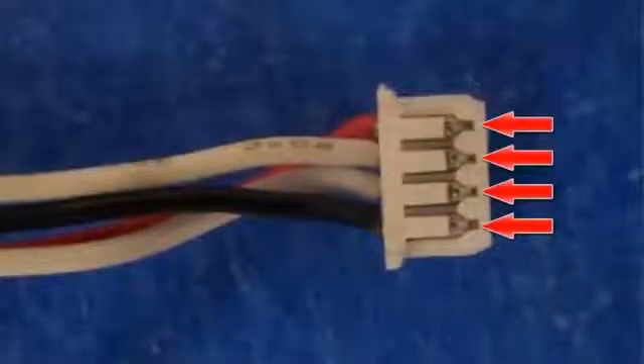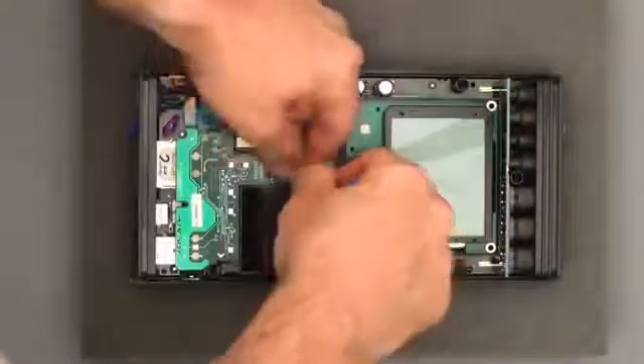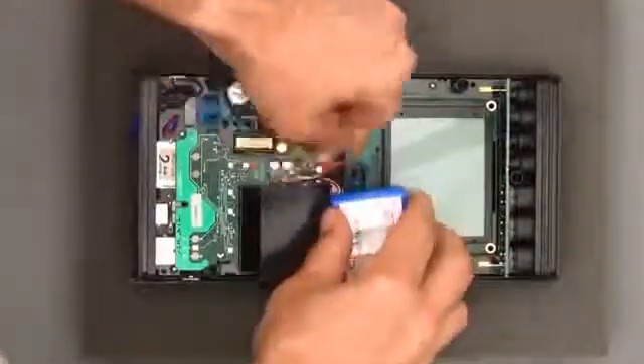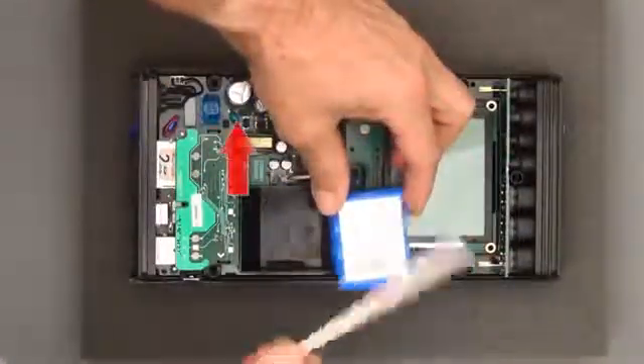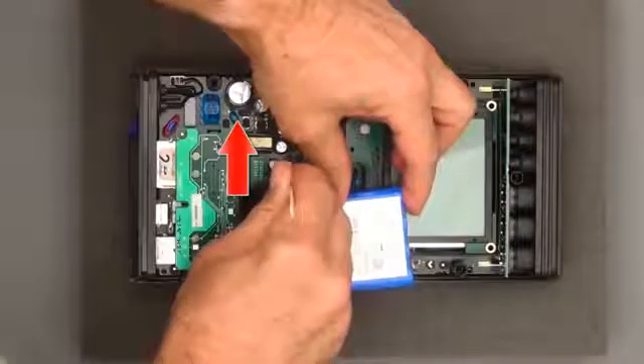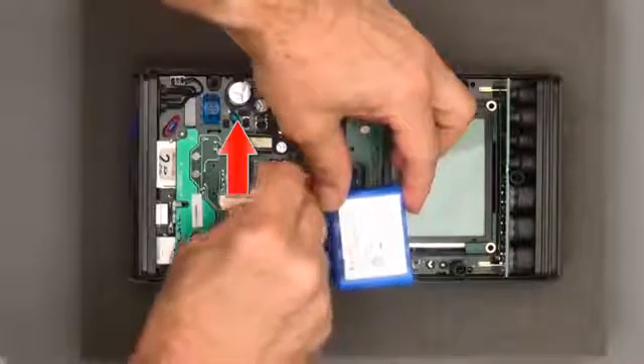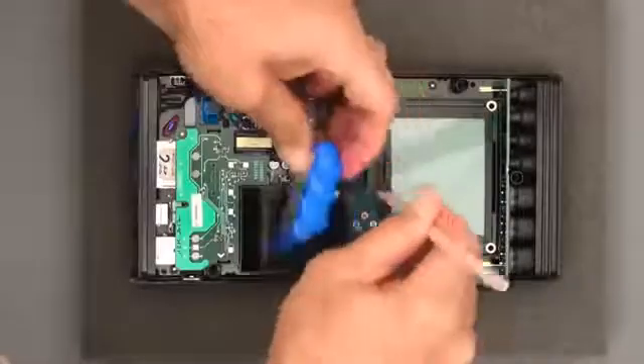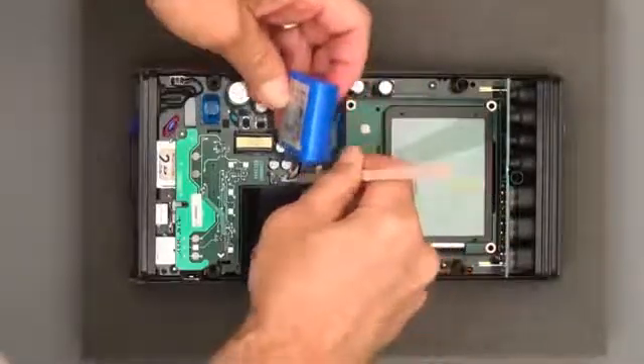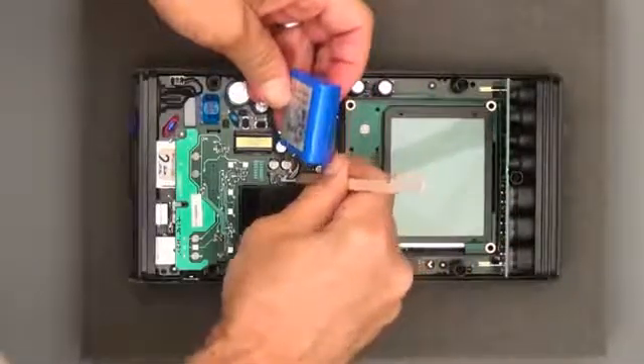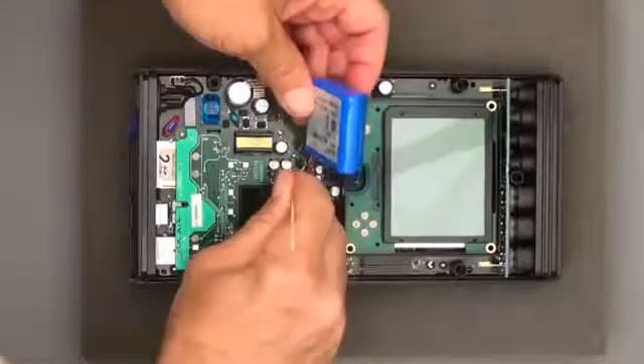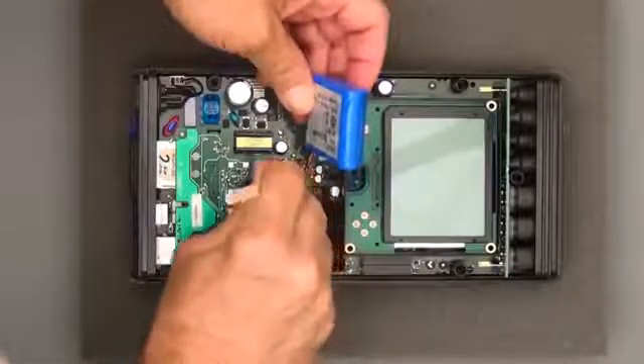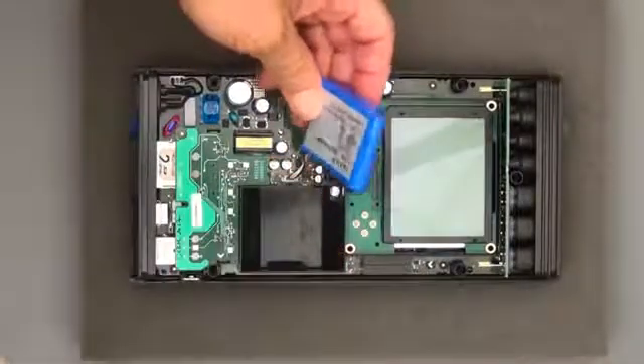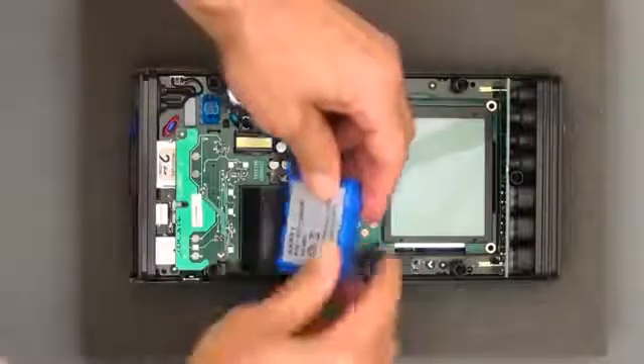Inspect the plug of the replacement battery pack and note the position of the connector pins. Position the plug with the connector pins facing away from the battery pack compartment. In the example shown on the screen, the pins are facing in the direction indicated by the arrow. Then very carefully insert the plug by gently pushing it into the socket within the PEL. There is very little room for this procedure, so an implement such as a drink stirring stick or toothpick may be helpful in ensuring the plug is securely inserted.